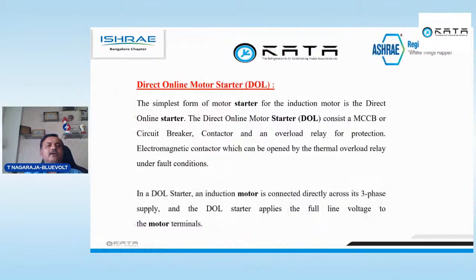Now we come to the starters. What is a DOL starter? The simplest form of motor starter for the induction motor is the direct online starter. That means the input will be 3 wires and the output will be 3 wires, up to a certain kilowatt. So in India, most starters will be DOL starters only up to 5.5 kilowatt.